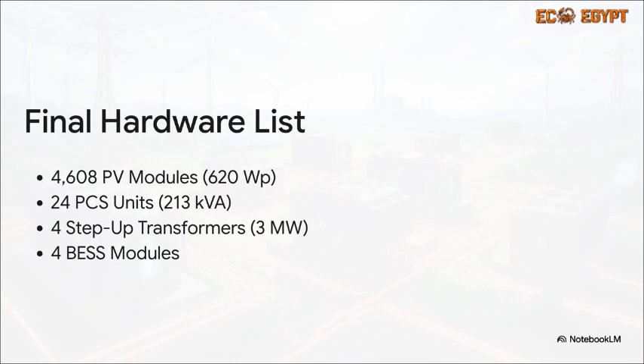And to supply that active power while also juggling reactive power for the grid at the exact same time, that takes some very serious hardware. The total apparent power required for this system hits approximately 43 megavolt amperes. So, to ensure a really healthy 3% design margin, that 20 megawatt-hour battery is paired with a massive 45 MVA bidirectional power conversion system and a matching step-up transformer. This is the heavy-duty equipment needed to instantly blast power back into the network the exact millisecond it is needed.